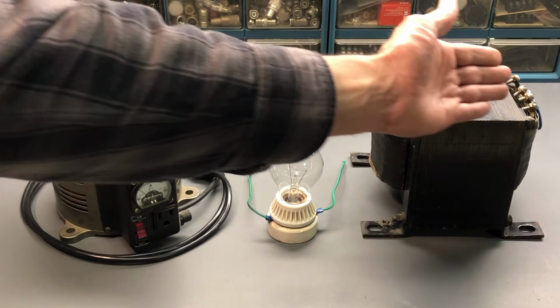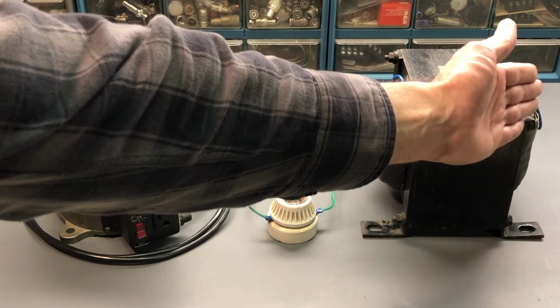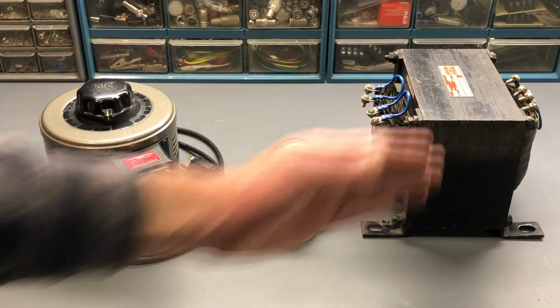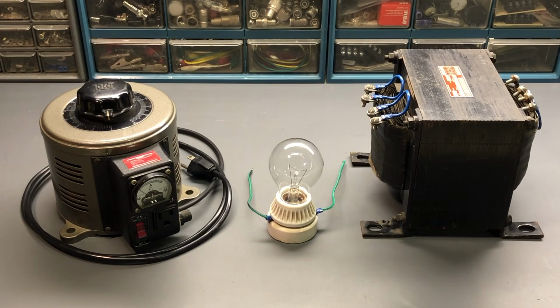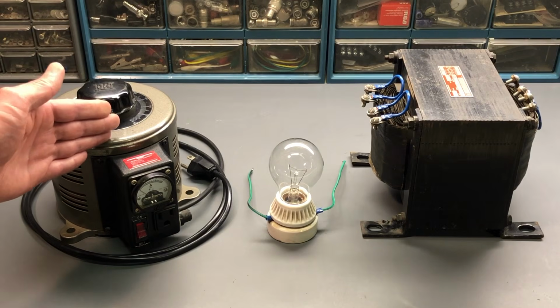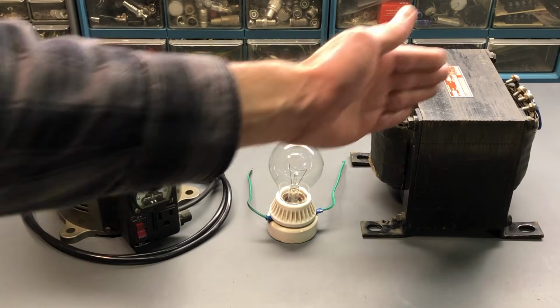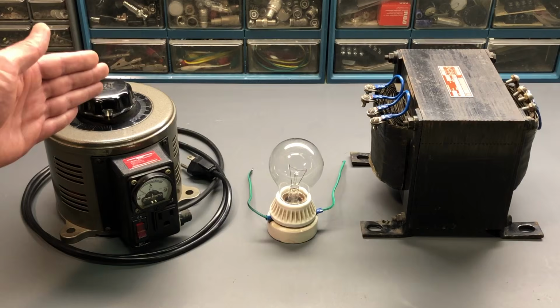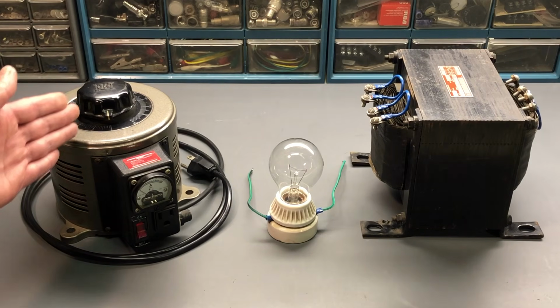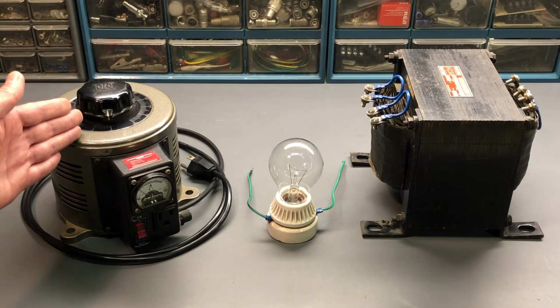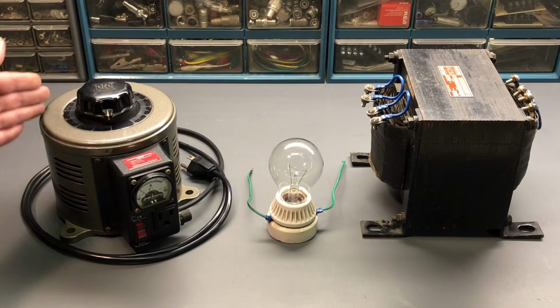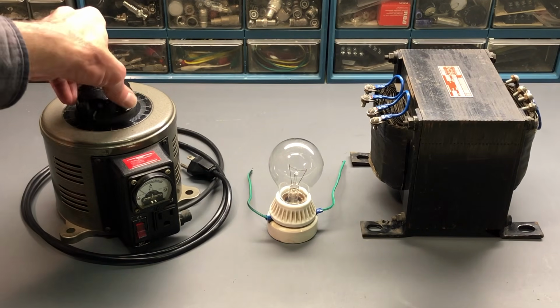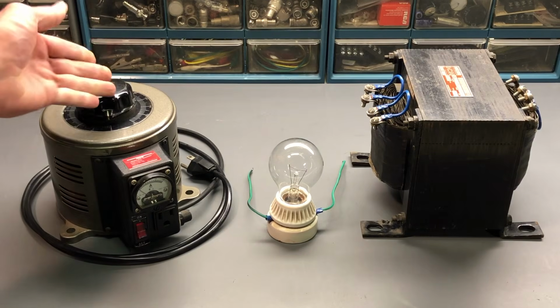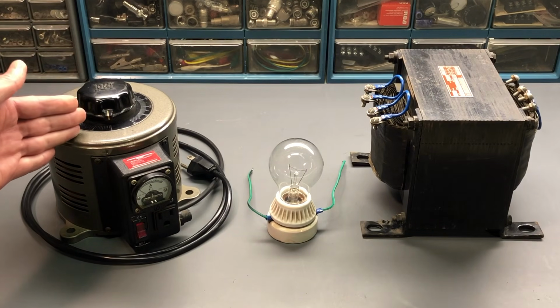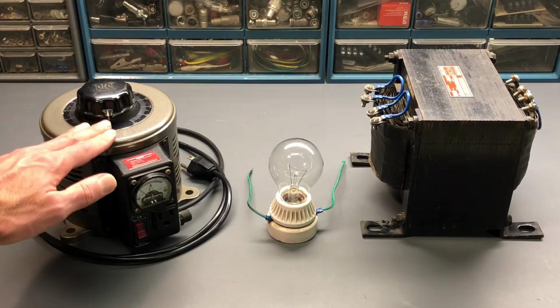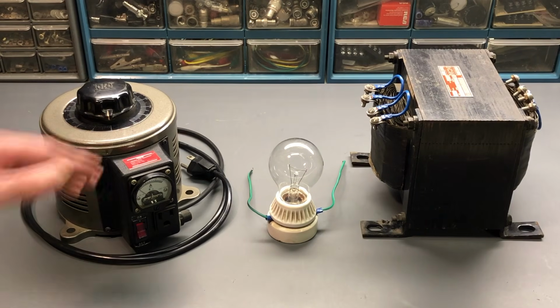Now, this transformer is a 1-to-1 turns ratio, so the voltage on the primary is the same as the voltage on the secondary. It's important to note that a Variac has no electrical isolation, all right? That's why this is required in addition to this Variac, which again has no electrical isolation. It's basically one continuous winding in here, and the knob that you turn is moving a variable tap on that winding, all right? So it's a type of autotransformer where the tap is adjustable.